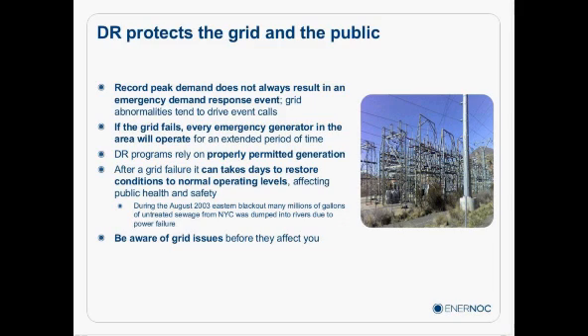And it's important to note that demand response enablement and participation does help save the grid, which actually helps reduce the need for all backup generators to run during a particular time. Because if the grid fails, all of these generators are coming on. Demand response allows a few generators to come on and help satisfy load requirements. DR programs rely on properly permitted generation. Before a site can participate in demand response, you have to make sure its permits are up to date for the particular jurisdiction and the particular type of use.